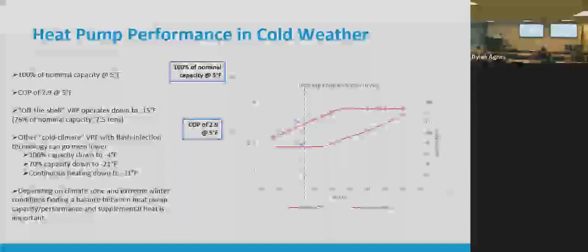And there was a couple weeks in Oregon where it never got above 15 in Portland and all the pipes were busting. That was 2 years ago. It was even colder in Bend, in the single digits for most of the week. And of course, our design day is 5.5. So when it's -5, -10 there, that's not what you designed for. Now the physics don't even matter anymore. So you're clearly undersized. But what we found when we've been super aggressive, and there's been abnormal events like the heat dome when it was 112 here, or in Portland, the system still performed.